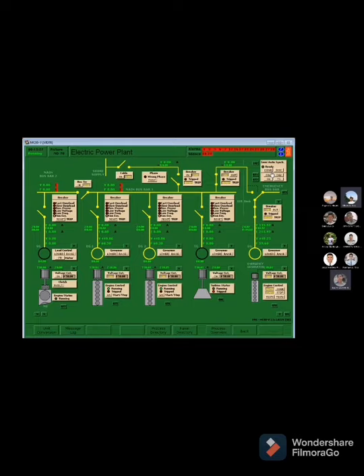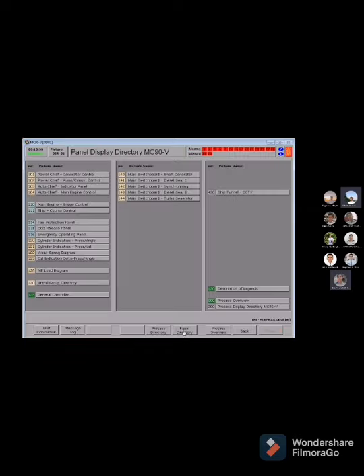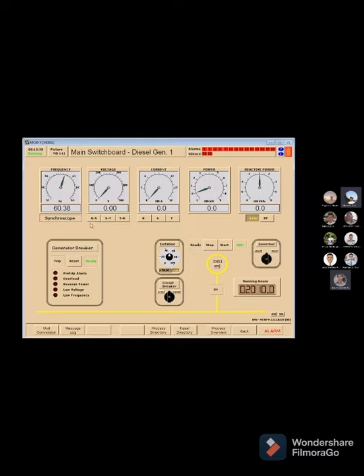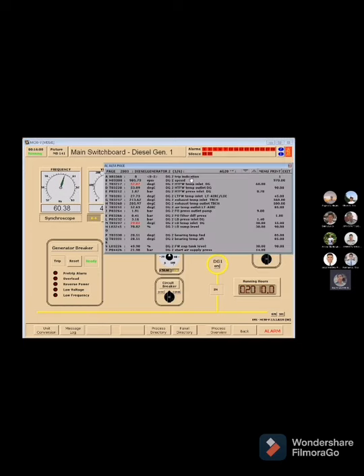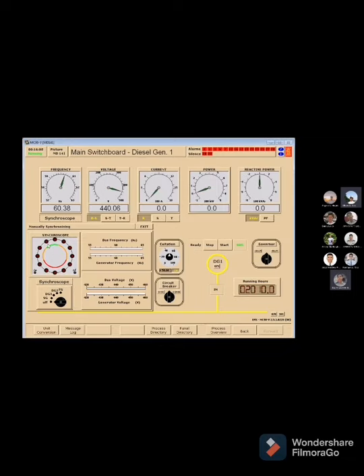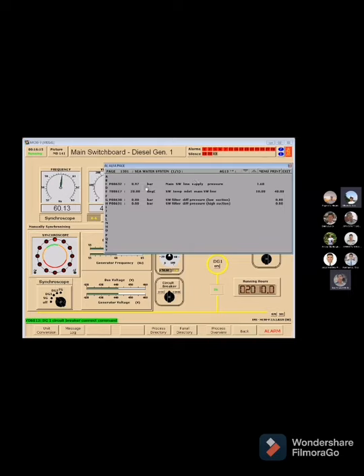Okay, the next step. Go to MD141, main switchboard. Then, diesel generator 1, check the frequency and the voltage by pressing either R-S, S-T, T-R, and current by pressing either RST. Okay, next. Press the synchroscope button and select DG1. Then connect the breaker. If there is an alarm, acknowledge it. Then next.